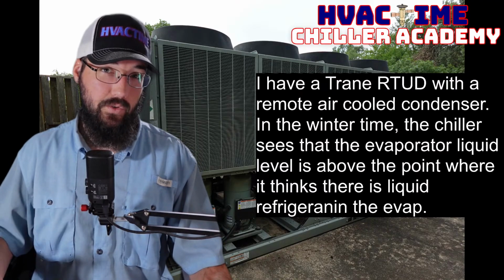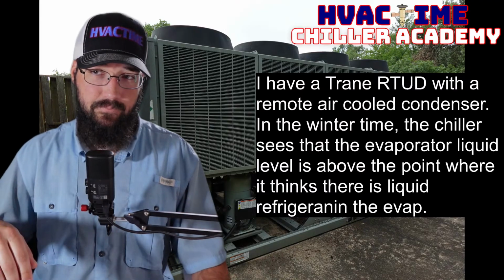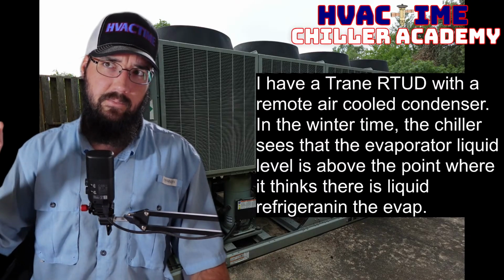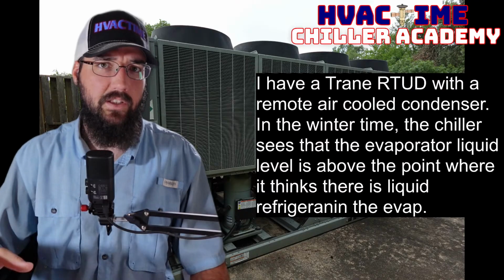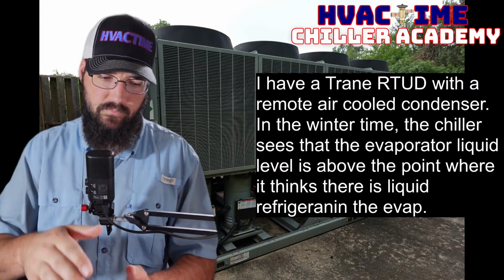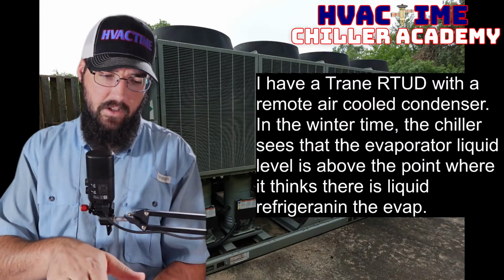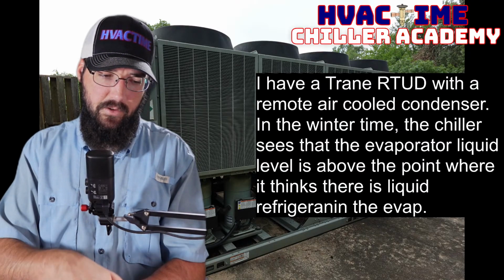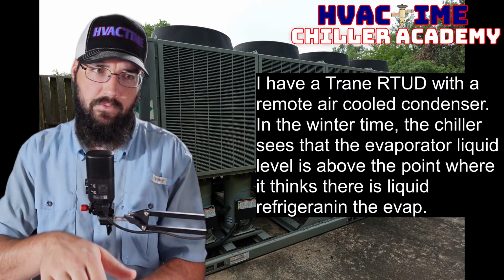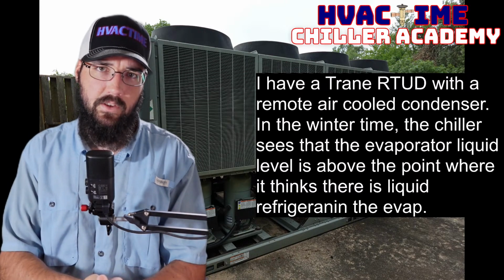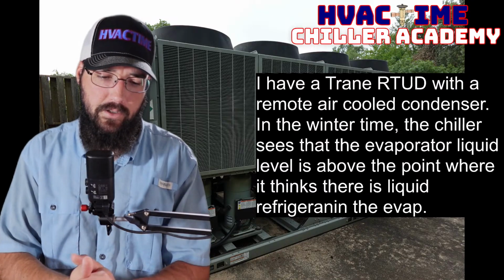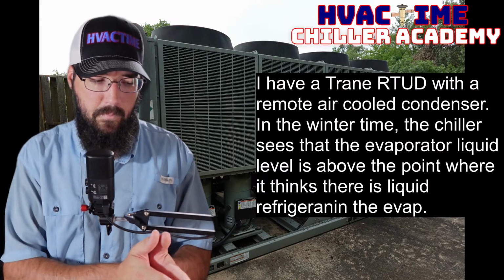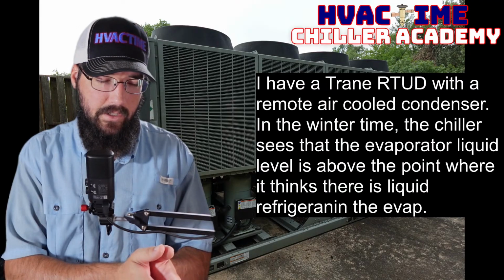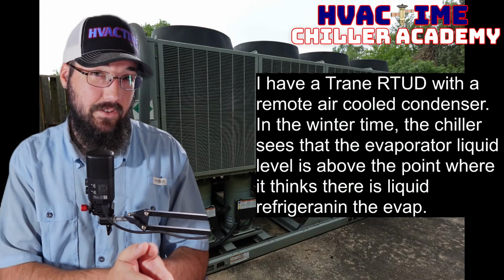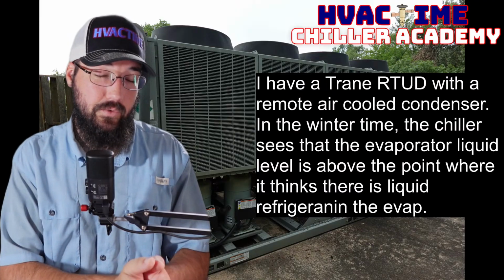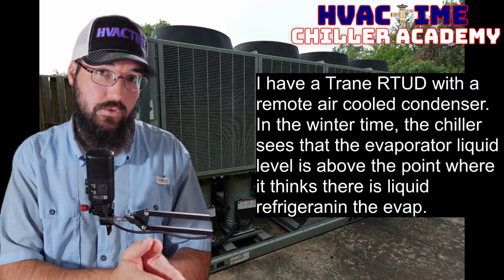Again, Trane's newer sensors, which are not the float style, are an actual solid state board that goes in to monitor the refrigerant through the continuity as it moves up and down. Same basic thing that YKs are using for their condenser liquid level. Either way, those are less susceptible, and I say less. I'm not going to say that they're not at all. They're less susceptible to that oil charge in there.